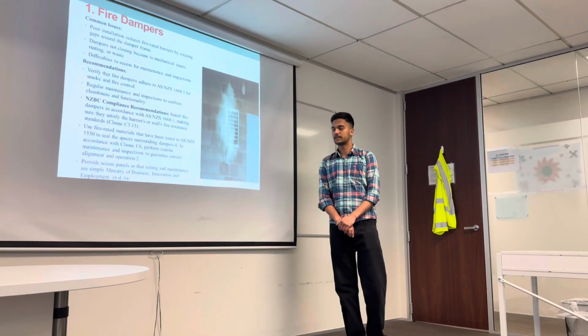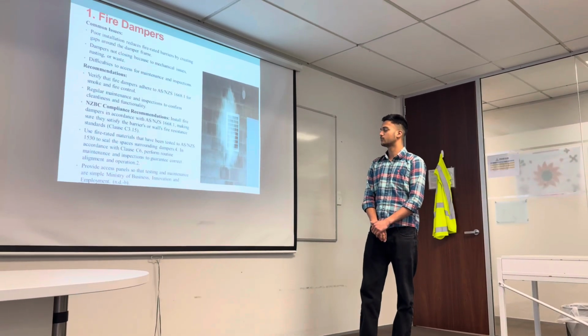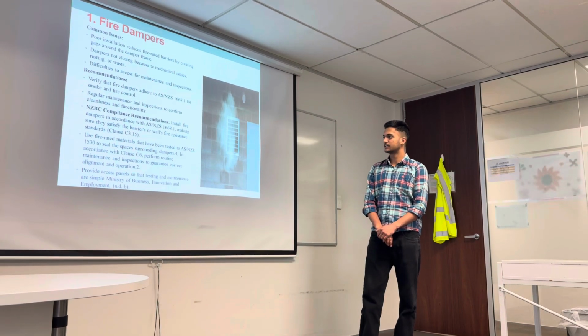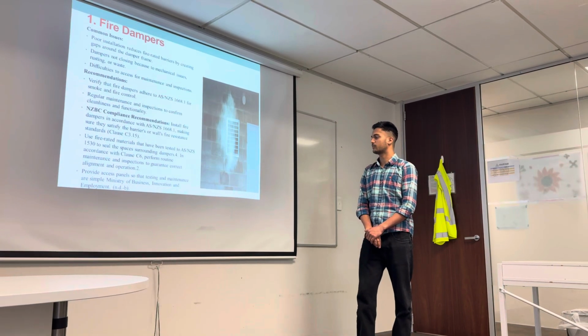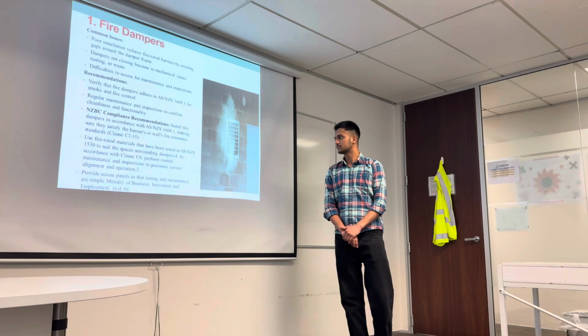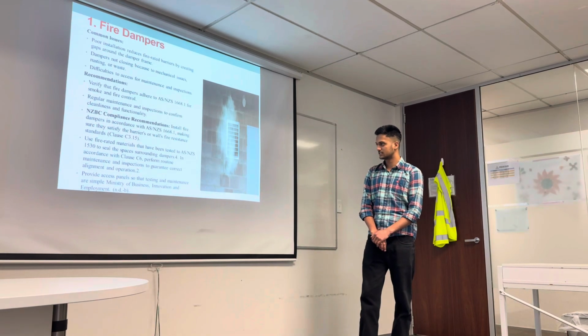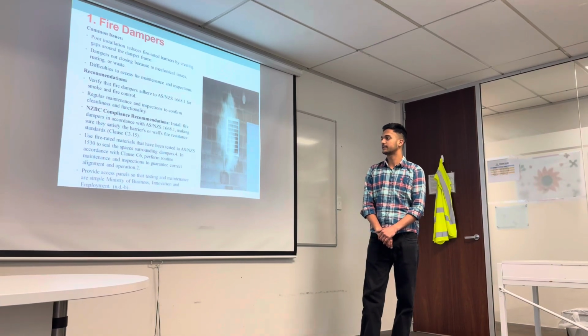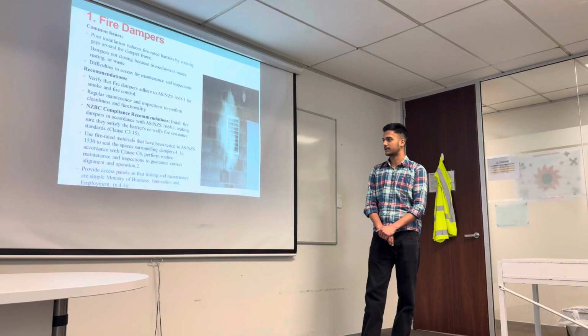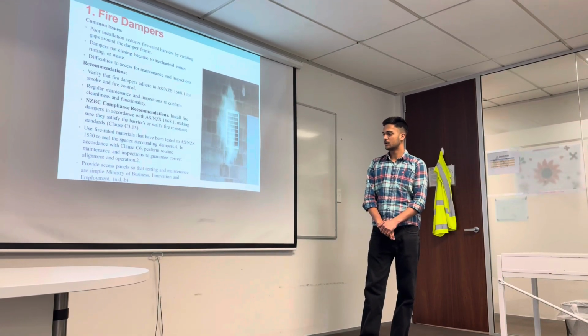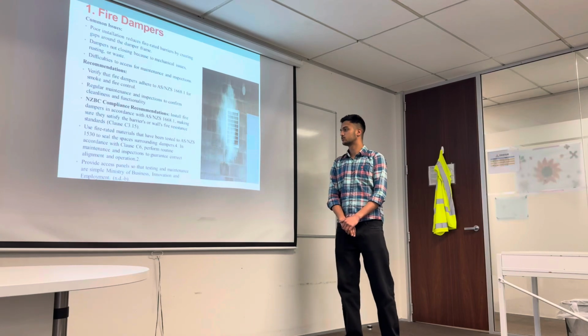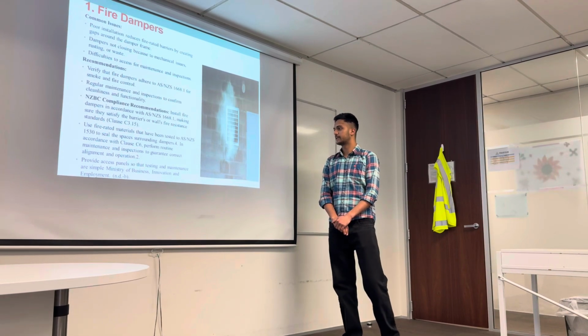Use fire-rated materials that have been tested to AS/NZS 1530 to seal the spaces surrounding dampers. In accordance with Clause C6, perform routine maintenance and inspection to guarantee correct alignment and operation, and provide access panels so that testing and maintenance are simple.